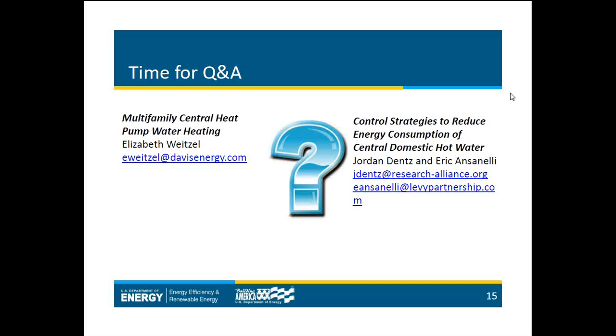And then another question, were domestic hot water distribution pipes insulated in the New York studies on the 4 buildings? In all of the buildings, the loops, the piping in the basement, the exposed piping was insulated. The risers in 2 of the buildings, buildings A and B, were not. They were older buildings. In buildings C and D, those pipes were well insulated, and it was only a 3-story building, so the risers were not recirculating. And that might partially explain the lower savings in buildings C and D. The recirculation loop was entirely insulated in those buildings.